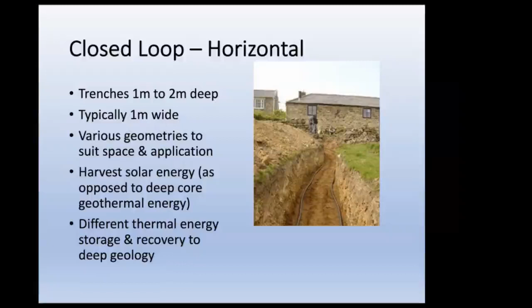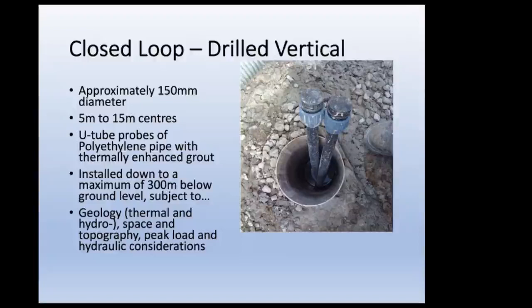So there's a vertical drill closed loop - conventionally 150 mil casing, 5 to 15 metre centres, and we go down to a maximum of 300 metres, but conventionally more like 150 to 200 metres, again depending on the geology. One of the disadvantages of ground source is the need for a feasibility study to be carried out, and those are expensive - at a commercial level very expensive - and they may in fact only go to prove that groundwater isn't feasible.